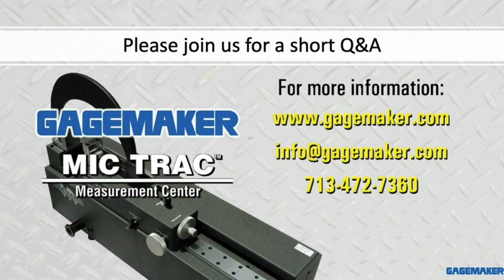Earlier in the webinar, you saw an example of something called a CRC, a calibration reference card. Those are available for free via request, and basically we give you a link, and you can download them. It's a procedure step by step, including using the Certify software, from beginning to end. So soup to nuts on that, basically cleaning the fixture, installing it, and calibrating using those CRCs. If we trained you to do it, we're going to use that exact same procedure. So the best way is to use the CRCs as orientation, and then on a daily basis, you'll be able to use that instrument. We sell hundreds of these a year, and people are able to do it on their own.